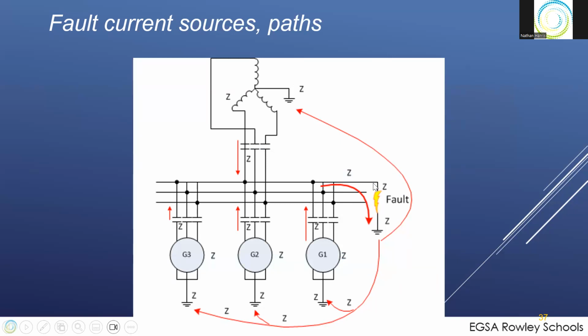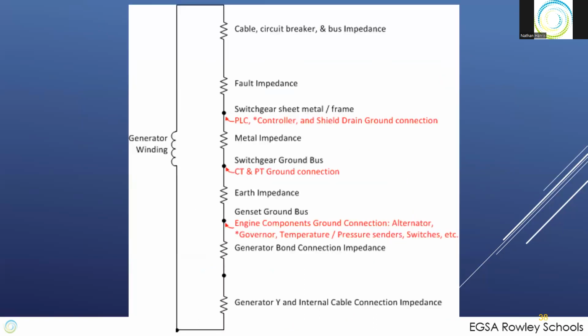And so you have a fault from A to ground, and through this fault the current comes back to the switchgear ground, switchgear frame to the bus, and then back to the neutral path. Of course, Kirchhoff says anything that goes out has got to come back. What goes out equals what goes in, and the current has got to flow back to the source. So let's look at just one leg of one generator in a parallel setup, and we'll look at the A phase.